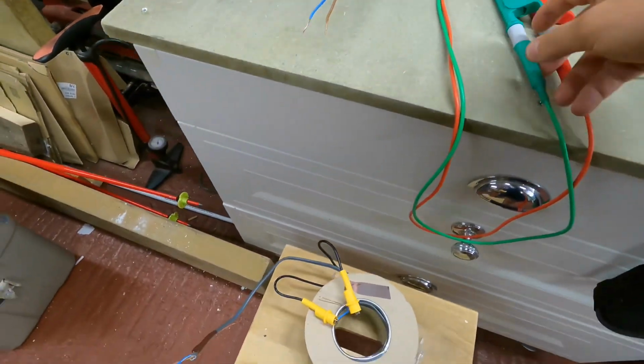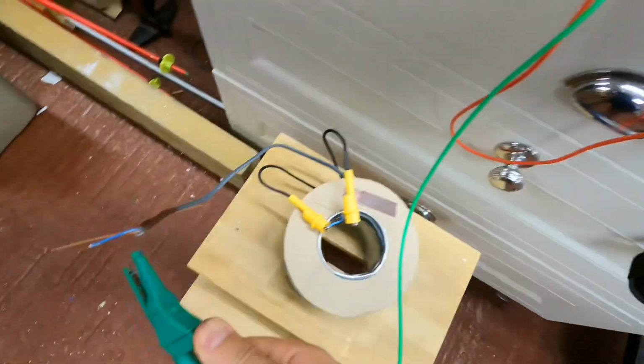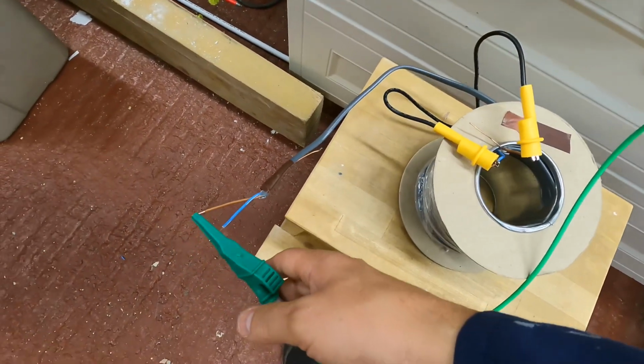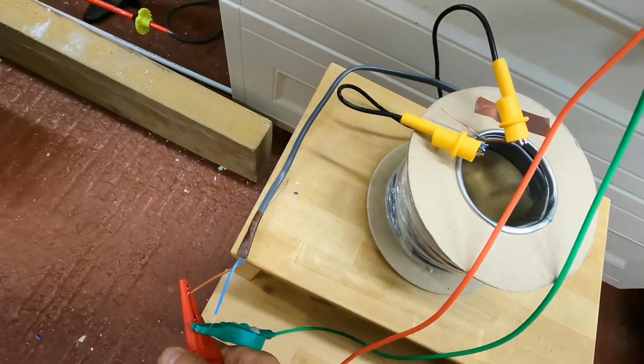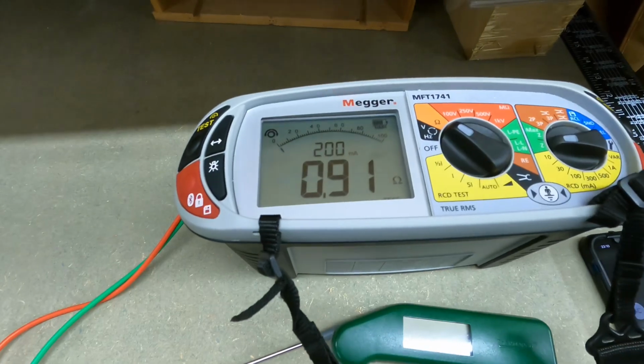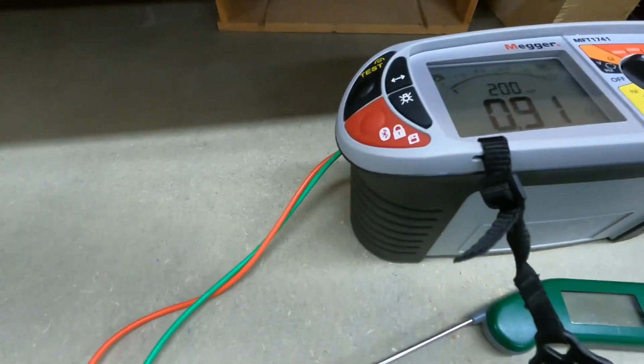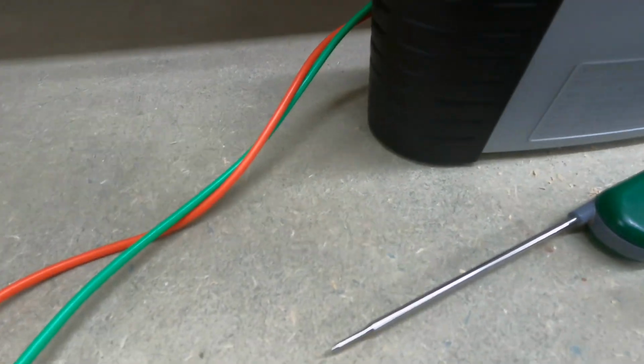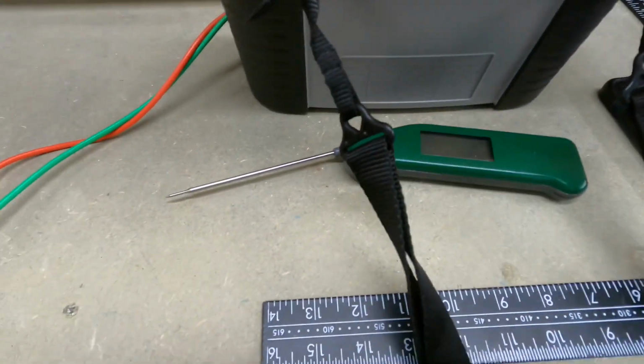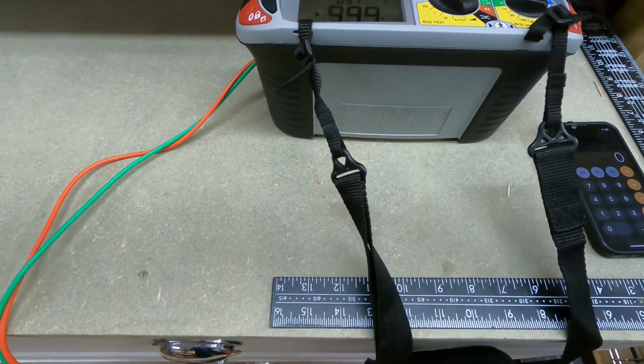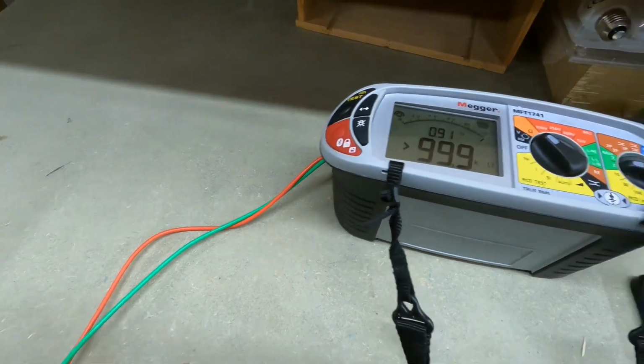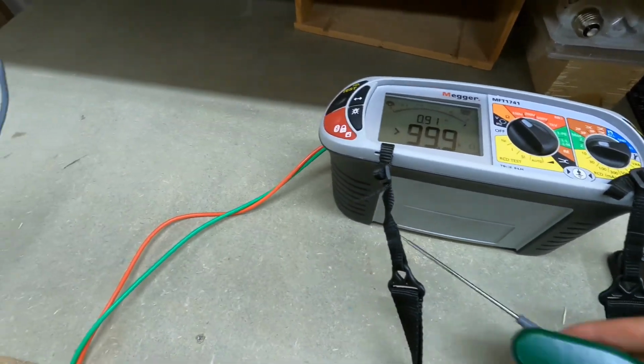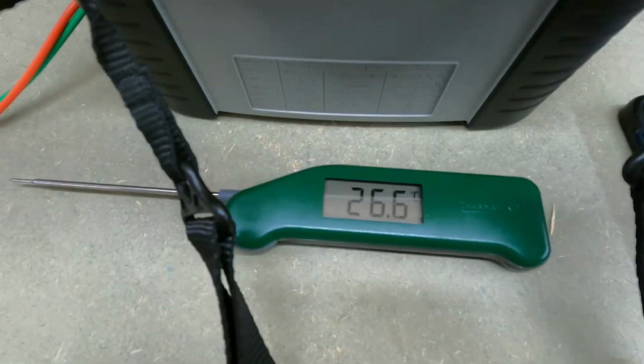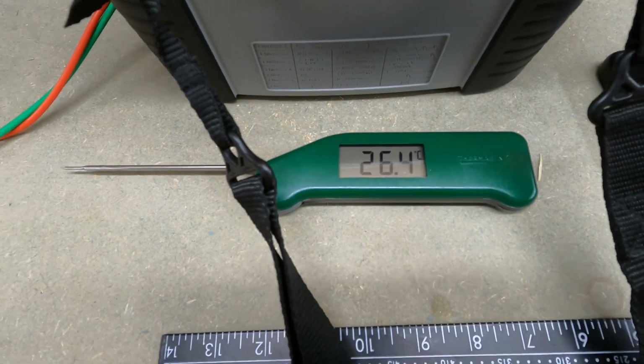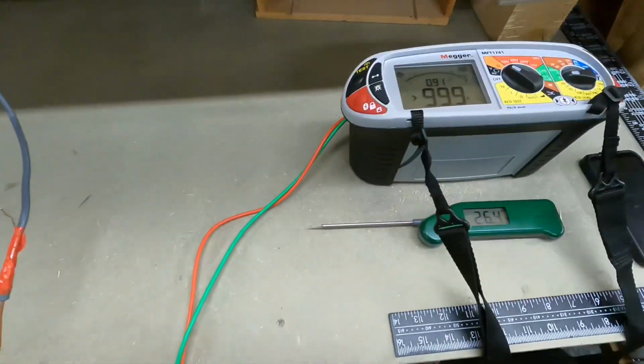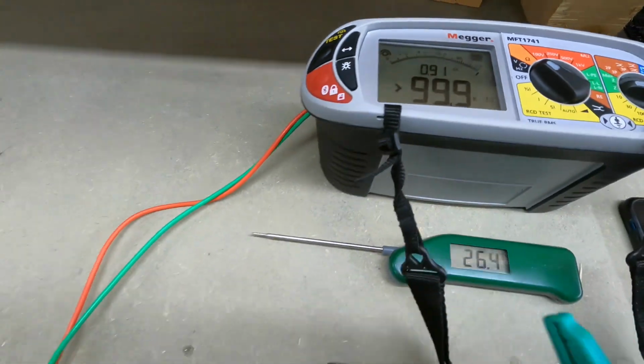Let's check in on resistances. I've zeroed the leads again, and we're now reading 0.91—a little bit warmer. I imagine the cable sitting out has warmed up a bit. I brought the temperature probe out, had to reset it; it's dropped to about 25.7-25.8 in here. So 0.91 for the room temperature cable.